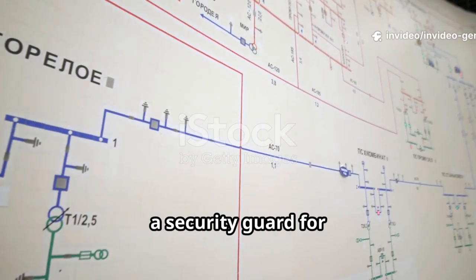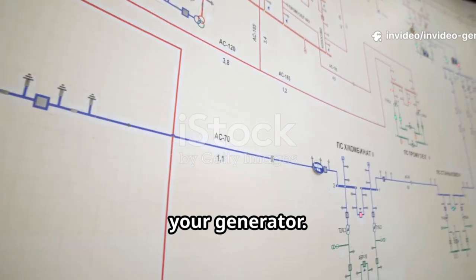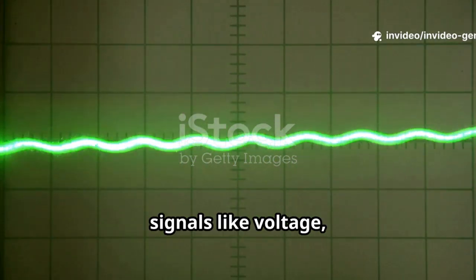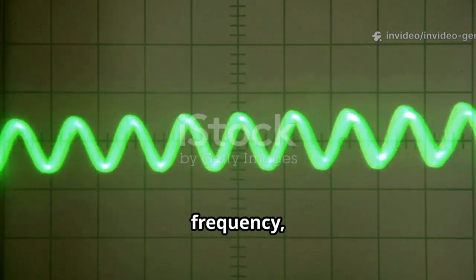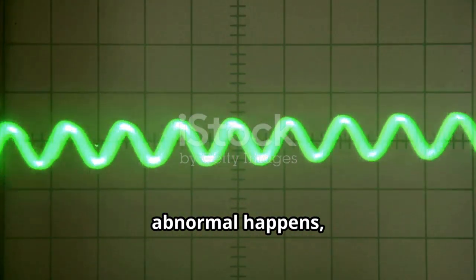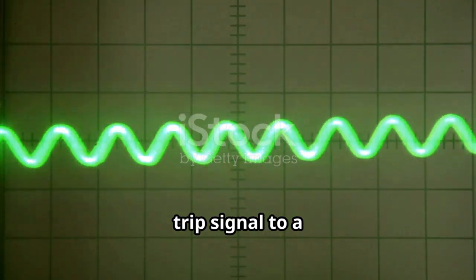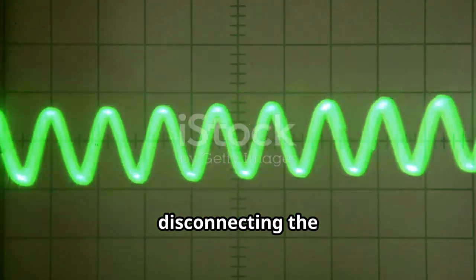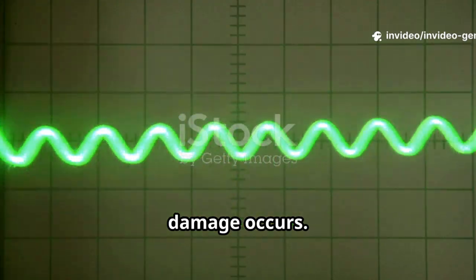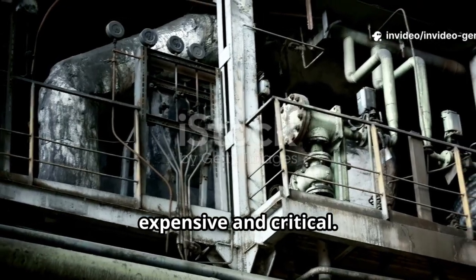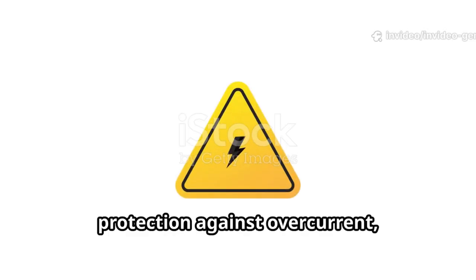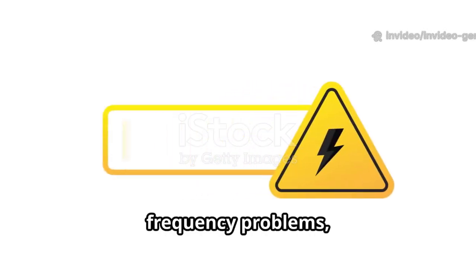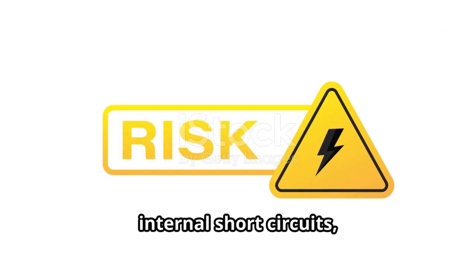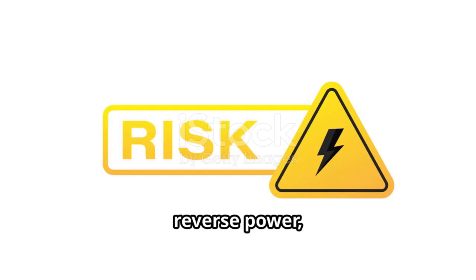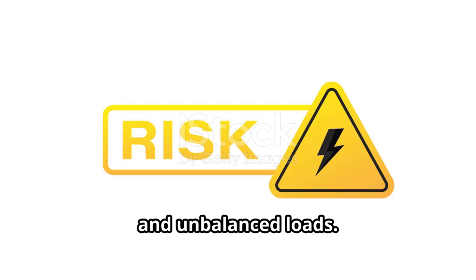Think of a relay as a security guard for your generator. Its job is to monitor electrical signals like voltage, current, frequency, and temperature. When something abnormal happens, the relay sends a trip signal to a circuit breaker, disconnecting the generator before damage occurs. Generators are expensive and critical. They need protection against overcurrent, overvoltage, undervoltage, frequency problems, internal short circuits, loss of excitation, reverse power, and unbalanced loads.